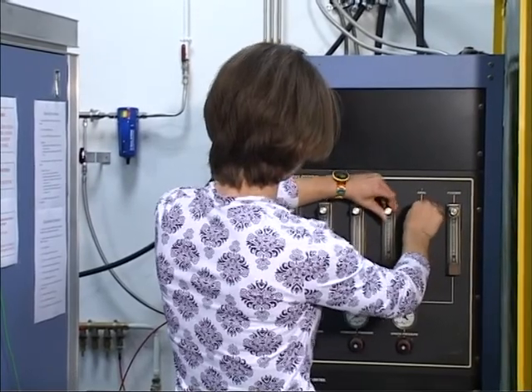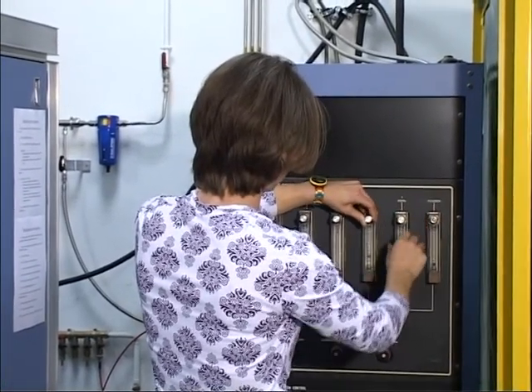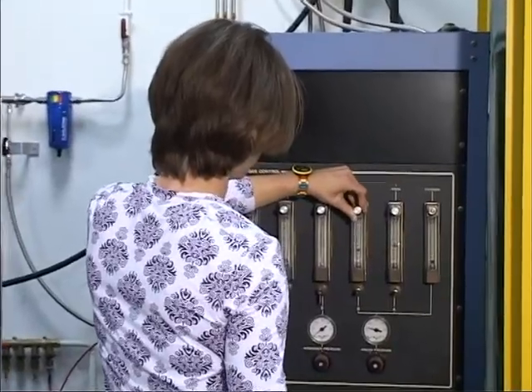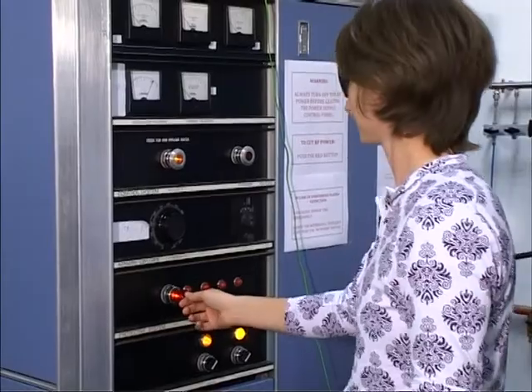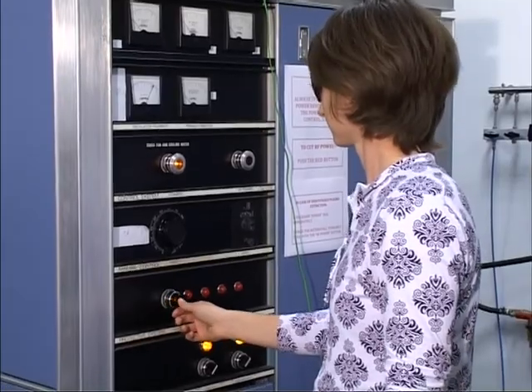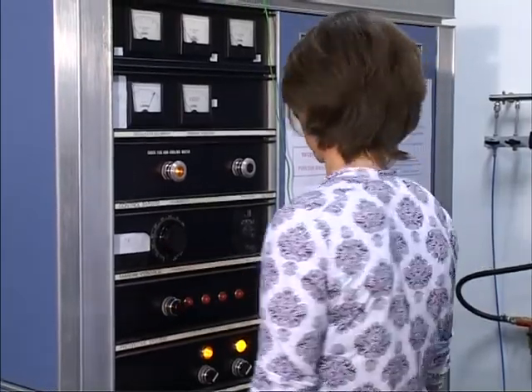We use argon for start-up because it is easily ionizable. When the red light comes on, warm-up is complete, and we do a final check of the safety and control panel, and then turn on the high voltage system.